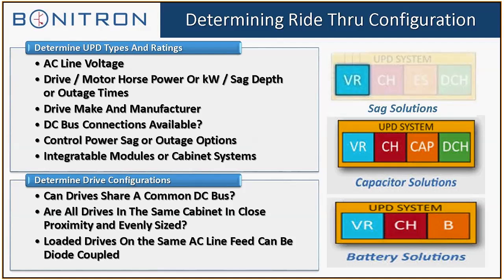Also, the AC line feeds. Of course, on a DC bus, all the AC line feeds are going to be common, but that's something important, especially for the sag ride-through. What we would do is total up the requirement for all of the drives on a ride-through common bus and size the ride-through to cover all of the kilowatt requirements for all the drives and motors.